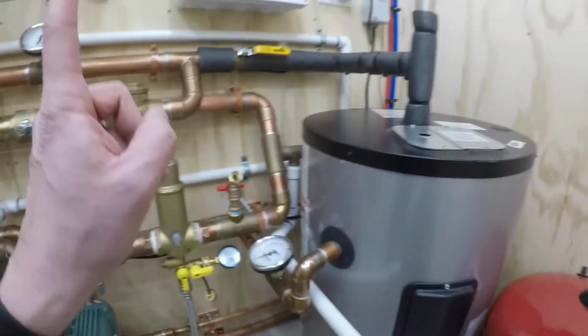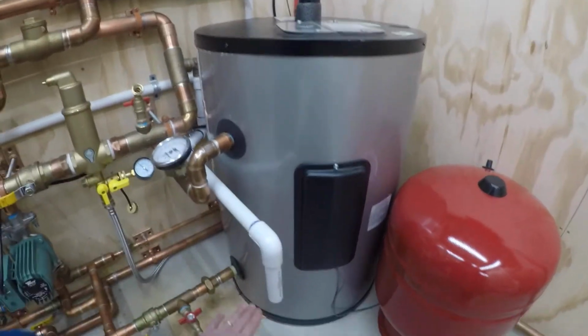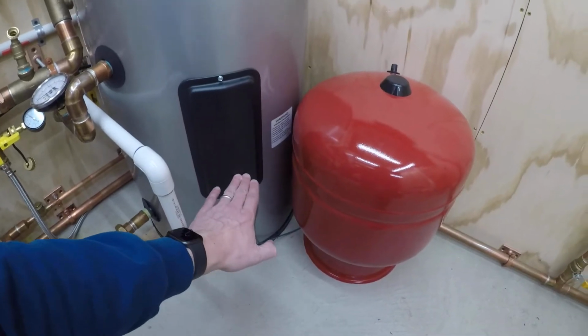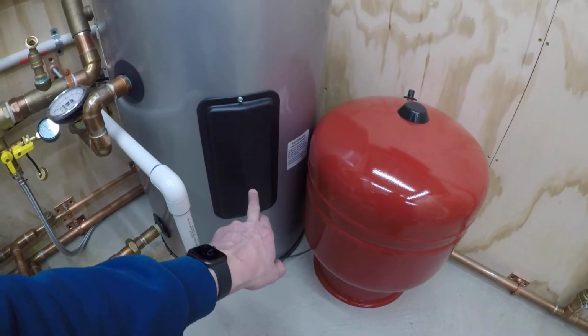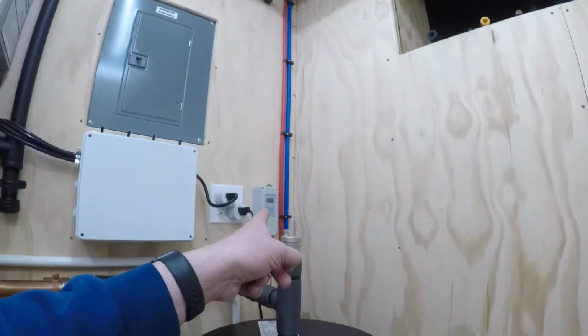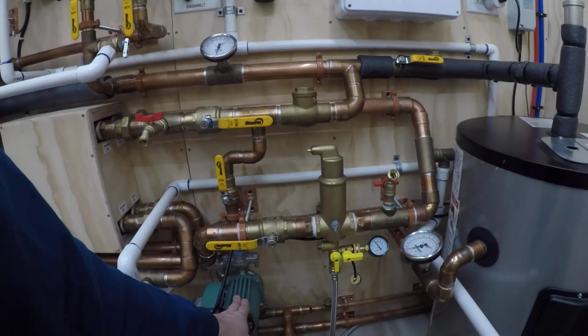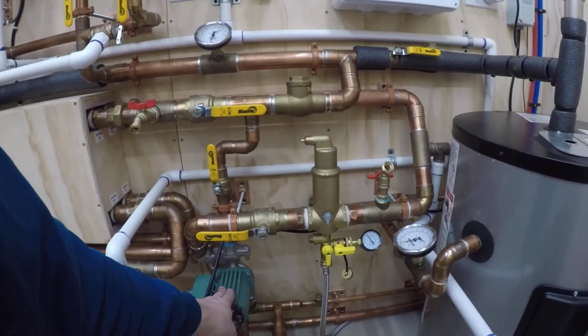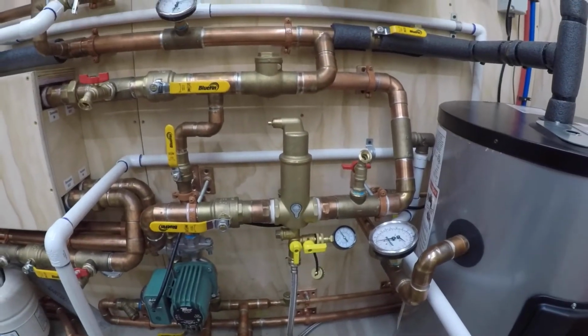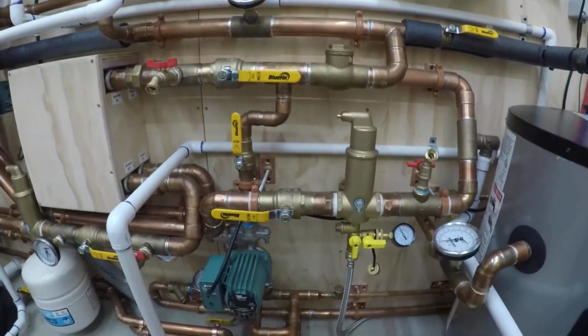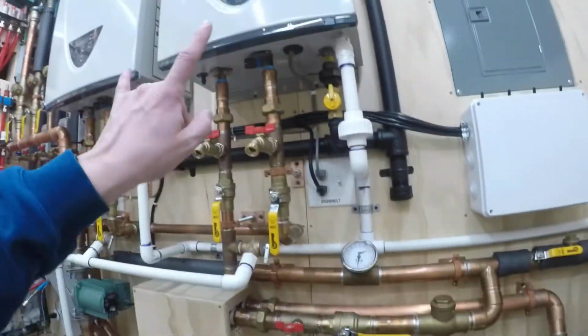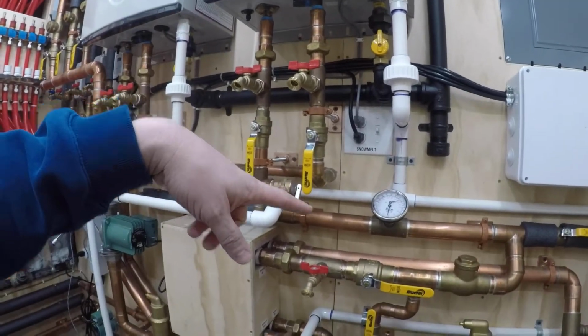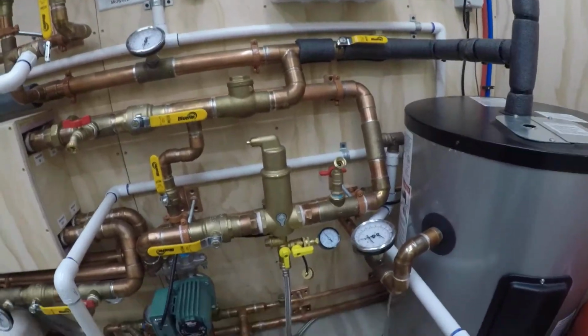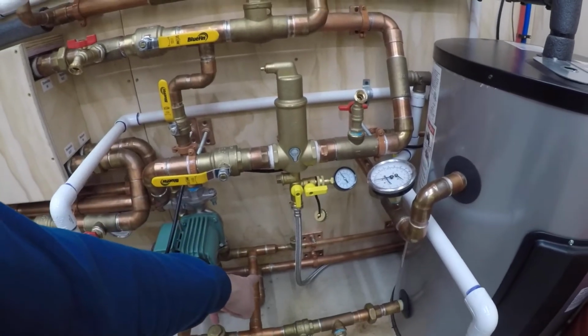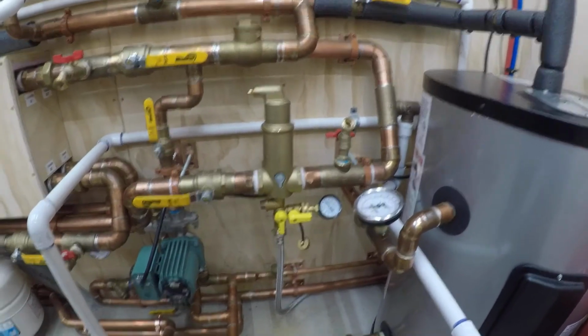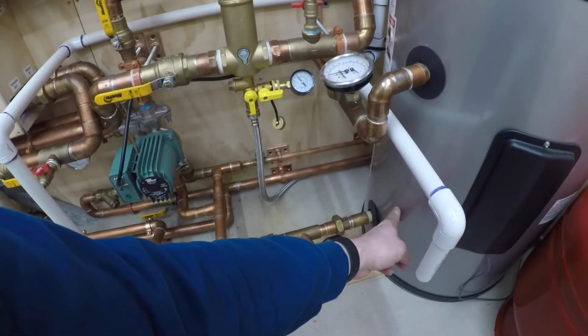So it's not going to fire the heaters initially, but eventually the cold water in this tank will start to replace the hot water up to a point where this sensor will drop in temperature and it will kick on the pump, just like it just did. But now, instead of pulling 100% of the roughly 7.6 gallons a minute that this pump can push through both of these heaters total, you're pulling 2.8 of it from the cold side to replace the 2.8 that's going out through the shower head. And the rest of it is coming from the tank.